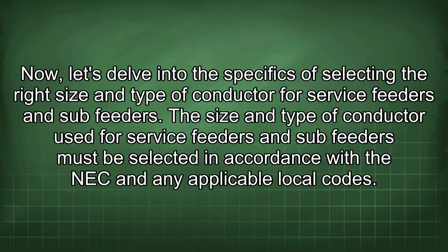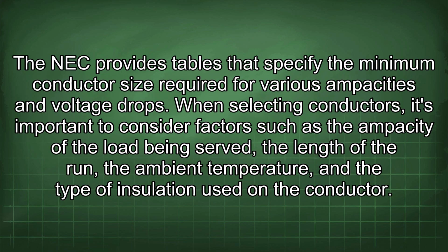The size and type of conductor used for service feeders and sub-feeders must be selected in accordance with the NEC and any applicable local codes. The NEC provides tables that specify the minimum conductor size required for various ampacities and voltage drops. When selecting conductors, it's important to consider factors such as the ampacity of the load being served, the length of the run, the ambient temperature, and the type of insulation used on the conductor.